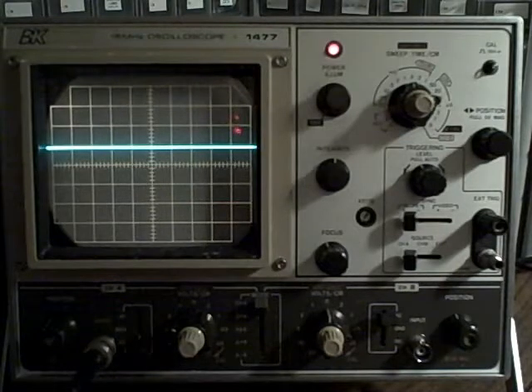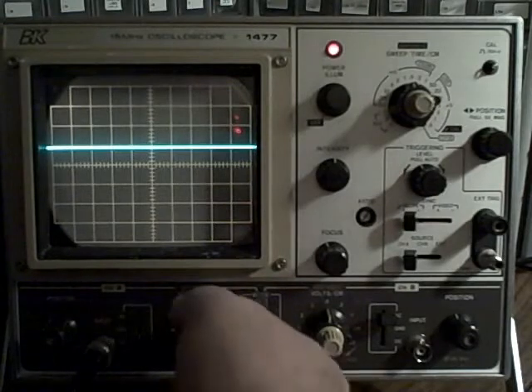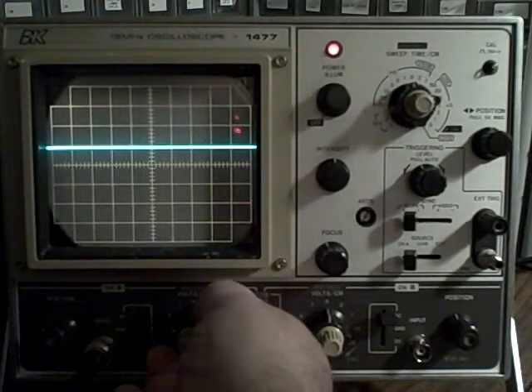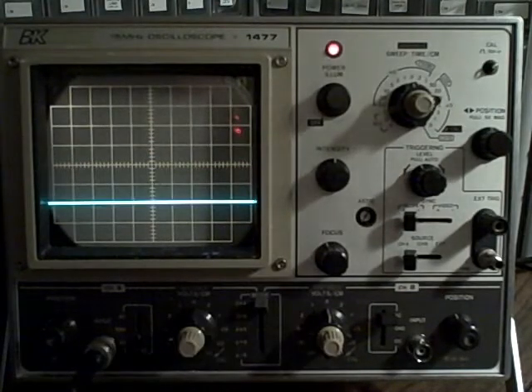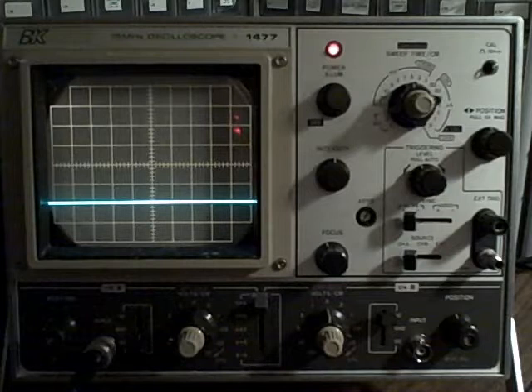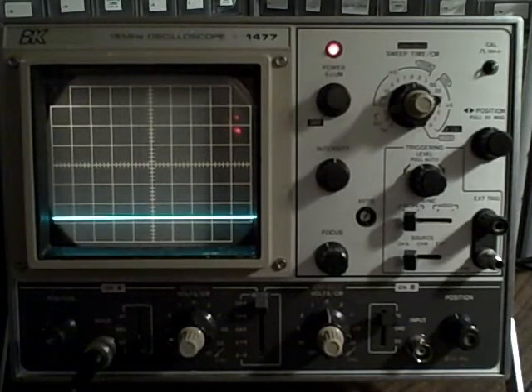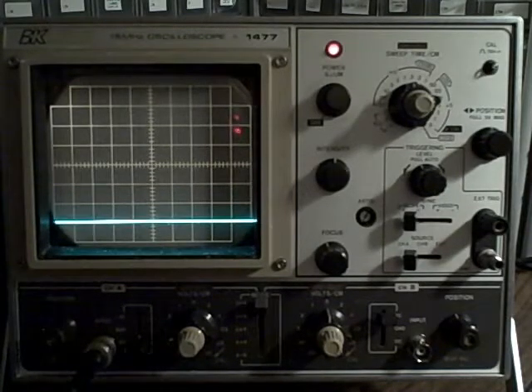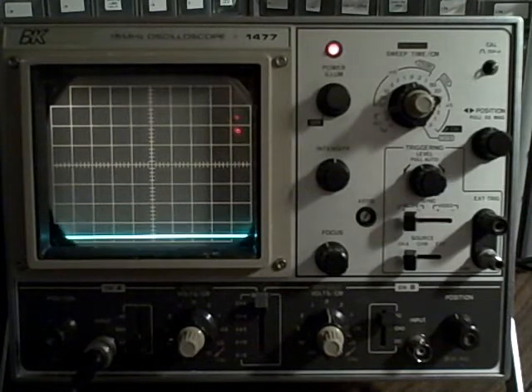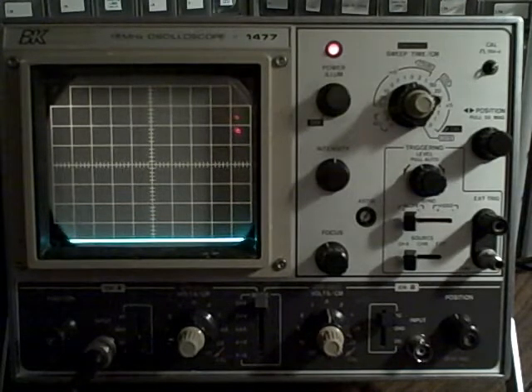Technically that's about all I can get out of this to display, so we'll stop with that one. If I go to 5 volts per division, I've got 10 volts coming in. I'm going to have 2 divisions on the display, and that's what I have. There's 5 volts at that point. I'm 1 division and 0.